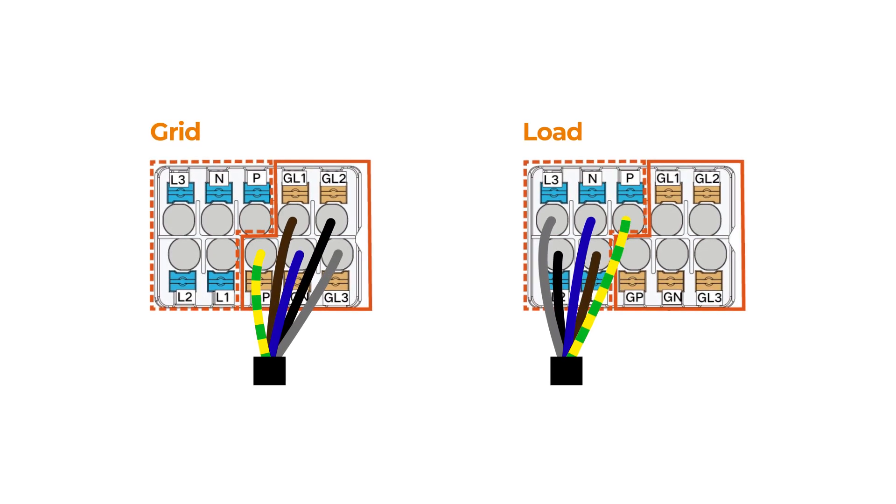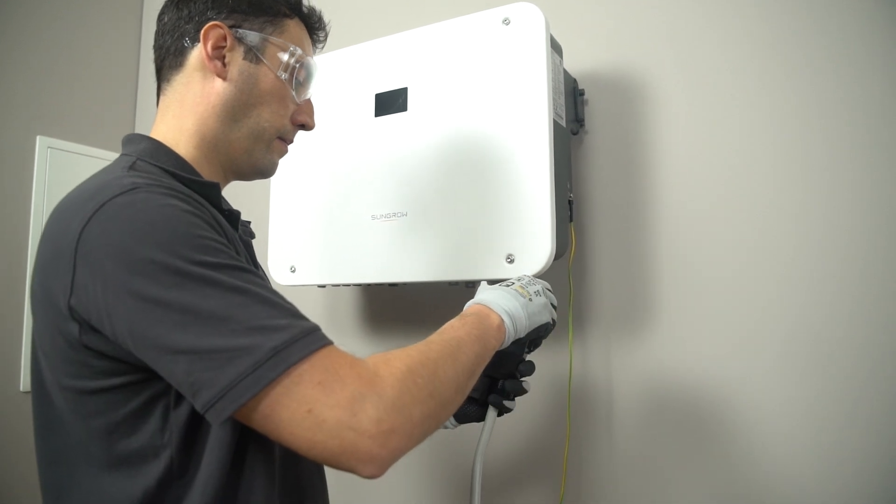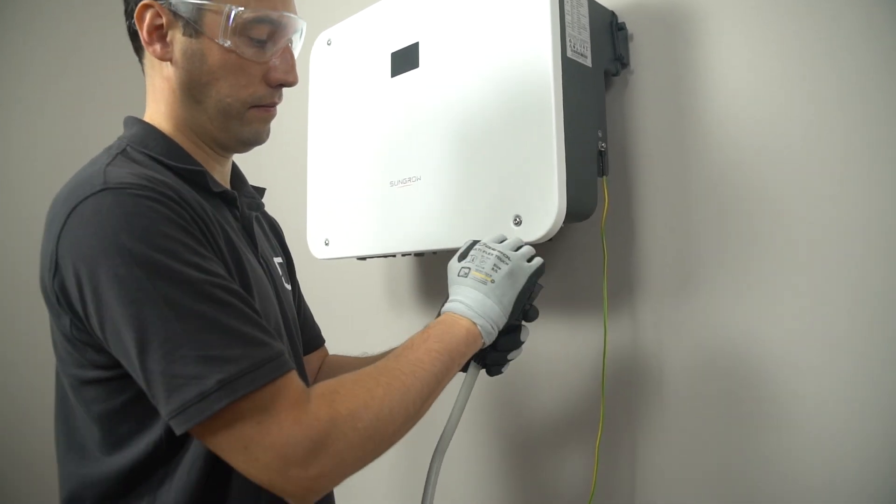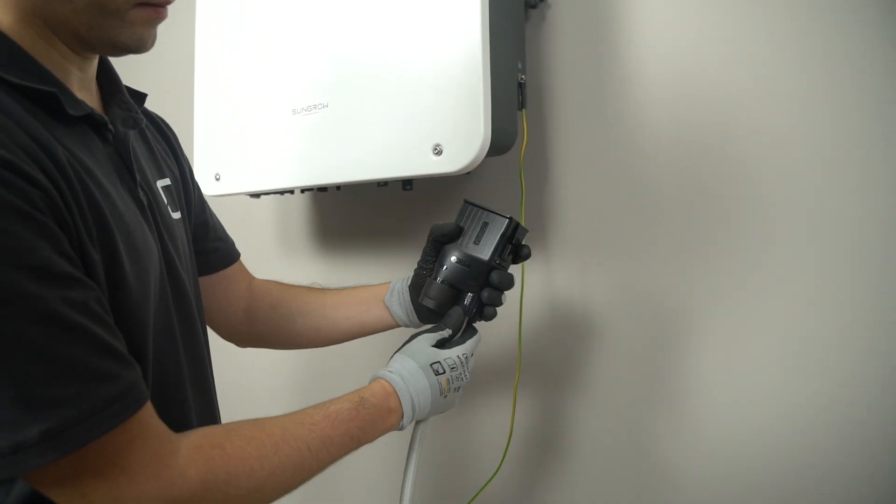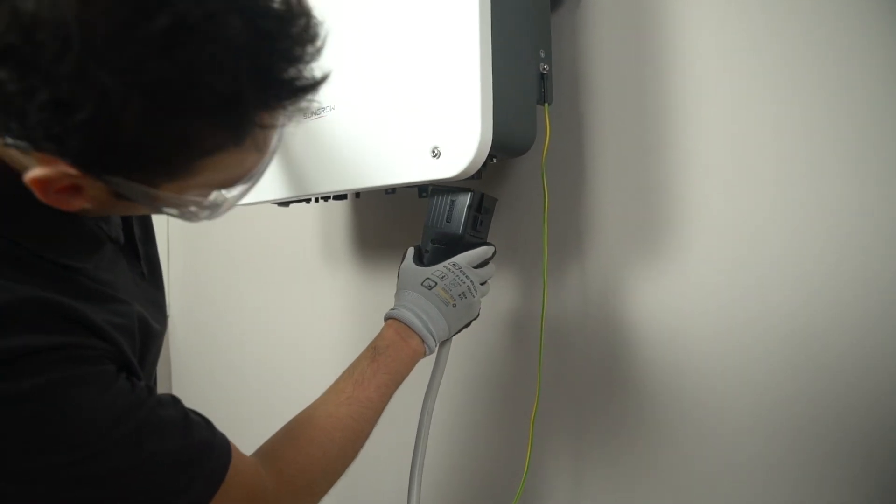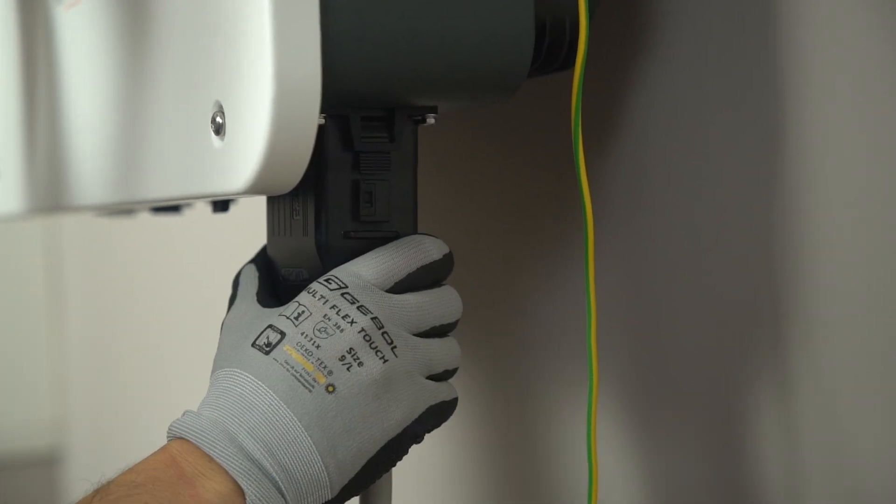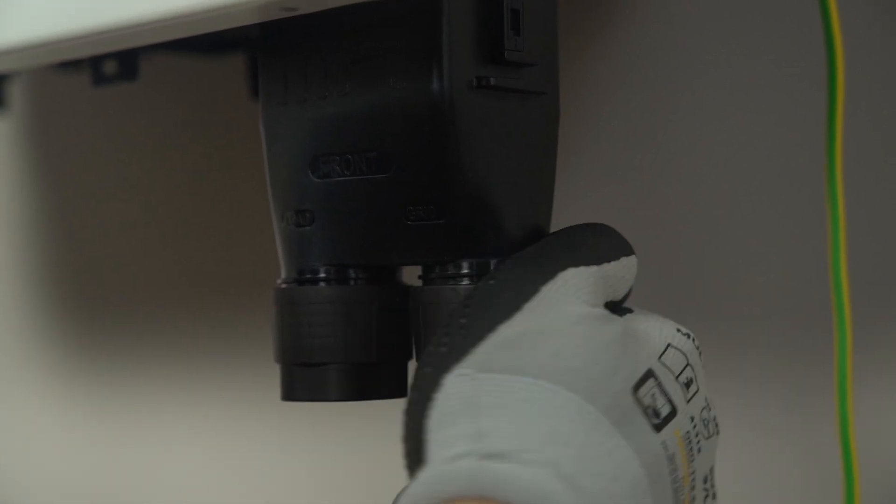After finishing wiring, make sure the cold pressed terminal does not protrude from the outside surface of the AC terminal. Ensure that the wires are securely placed by slightly pulling them. Insert the AC connector into the grid and load terminal on the inverter until you hear a click. Tighten the swivel nut to the housing. Lock the AC connector using a slotted screwdriver.